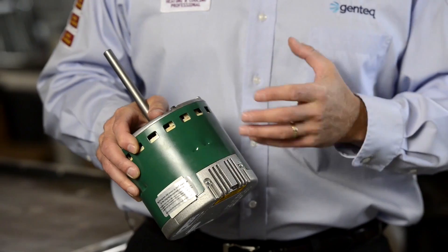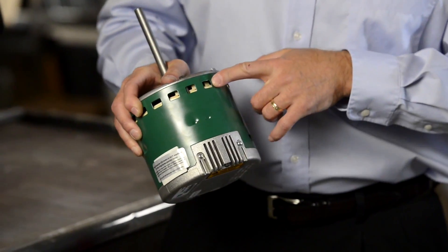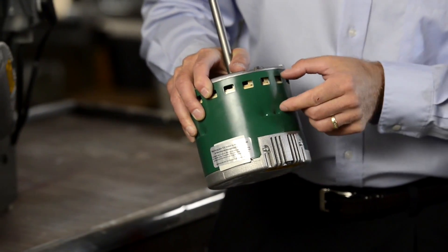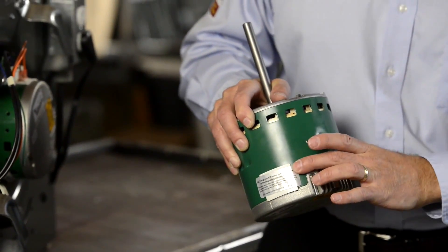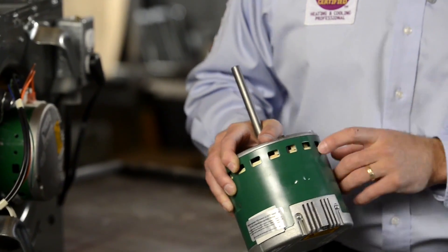One more thing to remember about putting a belly band mount around the Genteq ECM motor: notice that there are vent holes in the shell and also these little dimples in the shell. Between those two is where the motor mount should exist. Below the dimples is the open area of the motor shell where the electronics exist, and of course we never want to cover the motor vents.